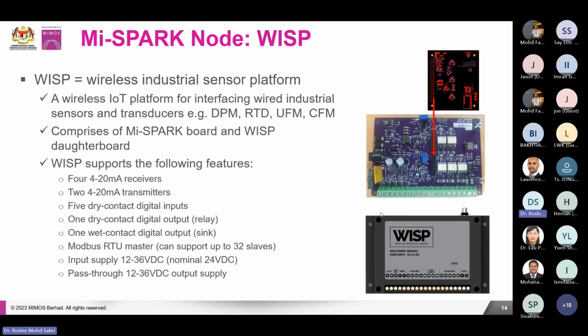For this particular product, because our original Mi-SPARK board doesn't have the Modbus or 4 to 20 milliamp interface feature, we developed another daughter board - the WISP daughter board - that we can plug into the Mi-SPARK board, since our Mi-SPARK board handles the computing and communication interface. We needed this for the wireless communication. What we've done is develop a daughter board that has all the interfaces allowing this product to connect to other industrial sensors and transducers, for example the DPM, the RTD, the UFM, and the CFM.